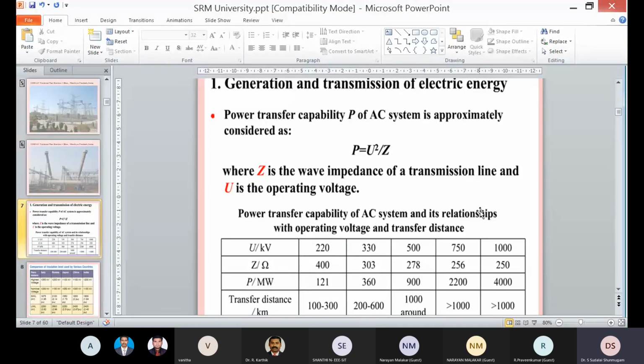Again, when it comes to power transmission, one of the key parameters that defines or limits the power transfer capability is your surge impedance. So I have given a table showing how the surge impedance defines the voltage carried in the line and also the power transfer. I have also provided a relation between system voltage and transfer distance. It's generally in the logic of 1 kV, 1 megawatt, 1 kilometer. Up to the first 3 segments, it will follow that category. The rest won't come under that category.